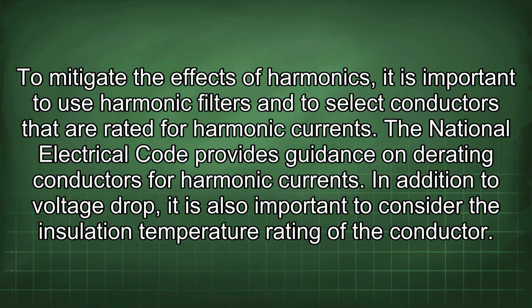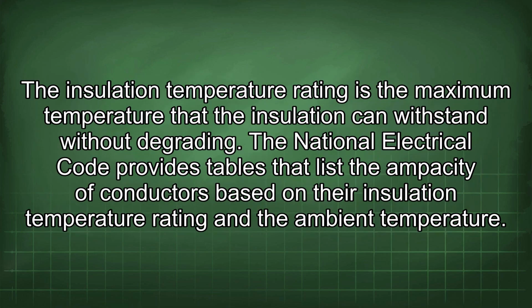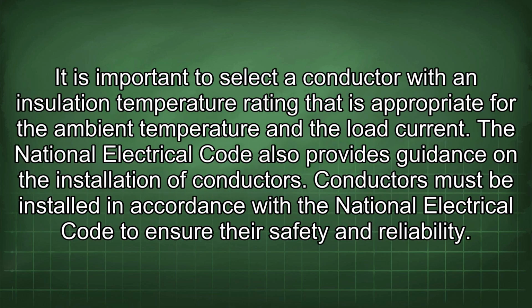In addition to voltage drop, it is also important to consider the insulation temperature rating of the conductor. The insulation temperature rating is the maximum temperature that the insulation can withstand without degrading. The National Electrical Code provides tables that list the ampacity of conductors based on their insulation temperature rating and the ambient temperature. It is important to select a conductor with an insulation temperature rating that is appropriate for the ambient temperature and the load current.